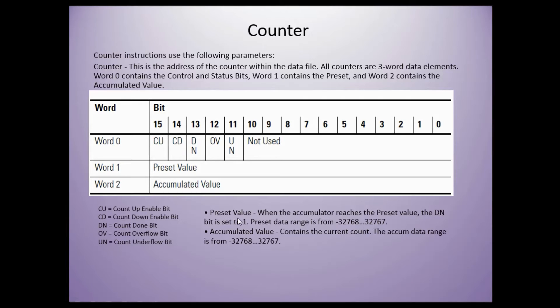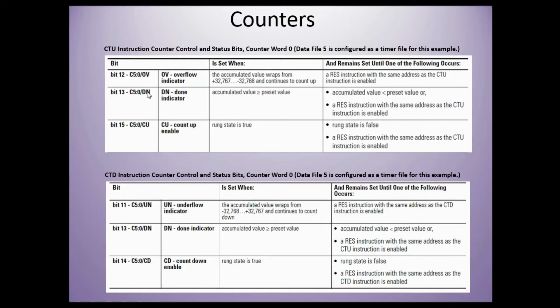The preset value: when the accumulator reaches the preset value, the done bit is set to 1. Preset data range is from negative 32,768 to 32,767. The accumulated value contains the current count. The accumulated data range is the same.